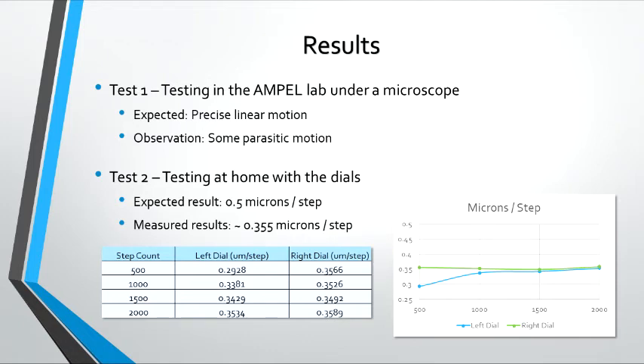This was calculated by taking a lot of measurements at different step counts. Notice how as the step count rises, the number becomes higher. However, even at 2,000 steps, the number is off from our calculated and expected value of 0.5 microns per step. There could be multiple things causing this, such as the dials not being very accurate, or that there are faults with the mechanical components or the motors. We could potentially fix this by adding in some microsteps to bring it down or up to an easier number to work with, such as 0.5 microns per step.